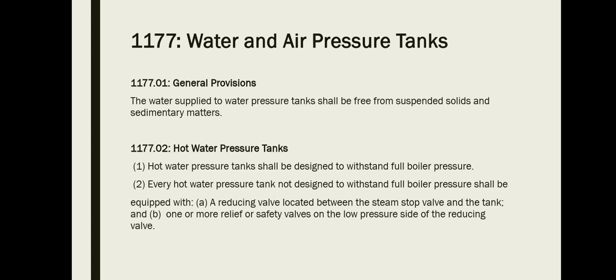Rule 1177.02, hot water pressure tanks. One, hot water pressure tanks shall be designed to withstand full boiler pressure. Two, every hot water pressure tank not designed to withstand full boiler pressure shall be equipped with A, a reducing valve located between the steam stop valve and the tank, and B, one or more relief or safety valves on the low pressure side of the reducing valve.